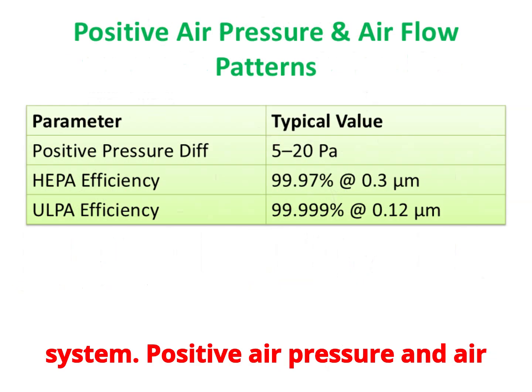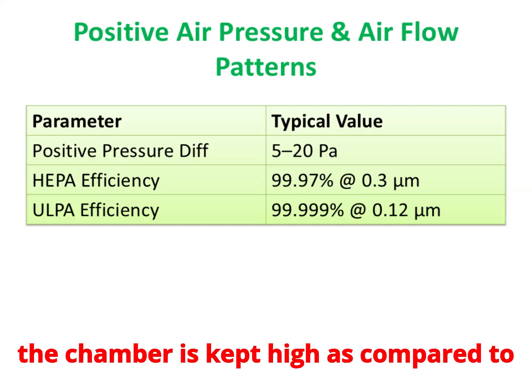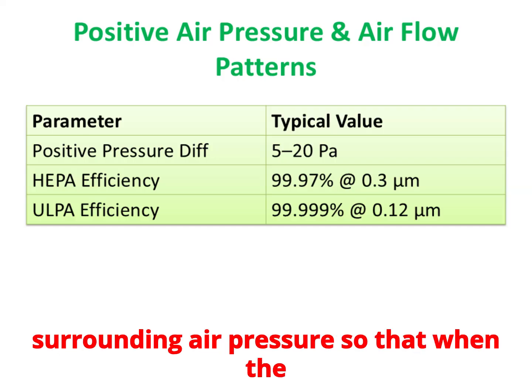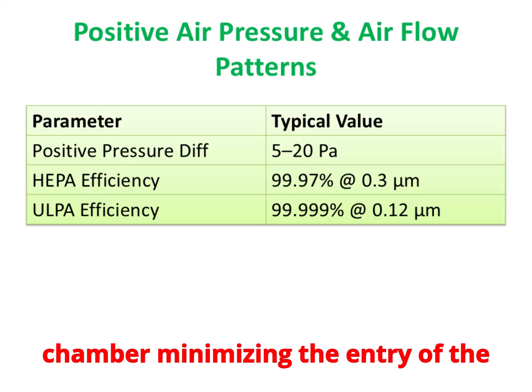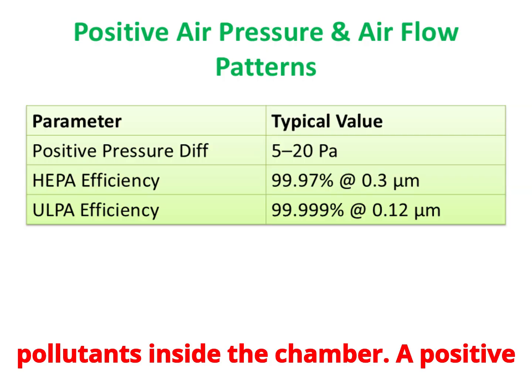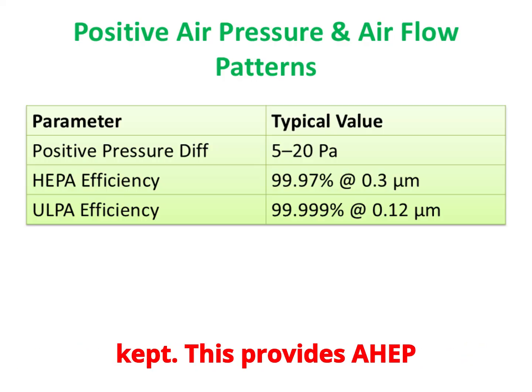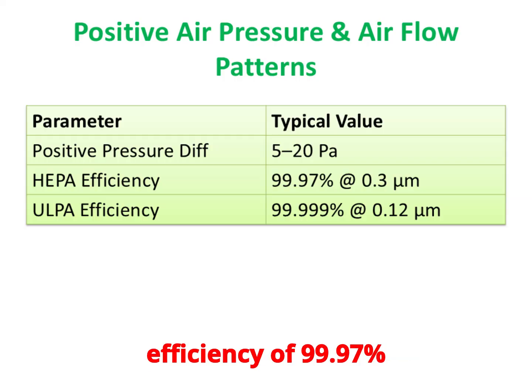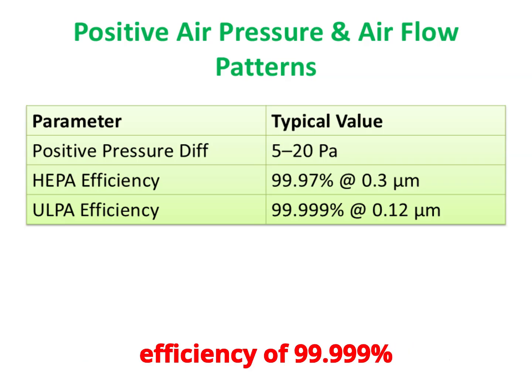The air pressure inside the chamber is kept higher than the surrounding air pressure, so that when the door opens, air flows out of the chamber, minimizing the entry of pollutants. A positive pressure difference of 5 to 20 Pascals is maintained, providing HEPA efficiency of 99.97% for 0.3 micrometer particles and ULPA efficiency of 99.999% for 0.12 micrometer particles.